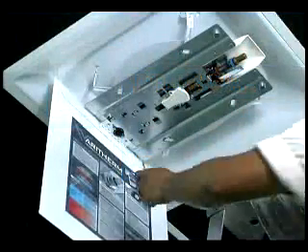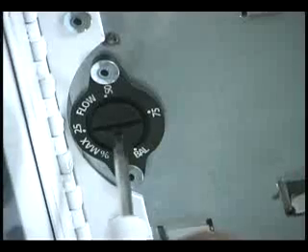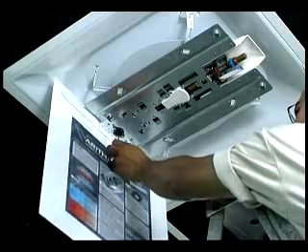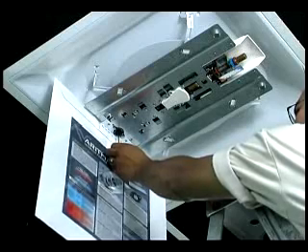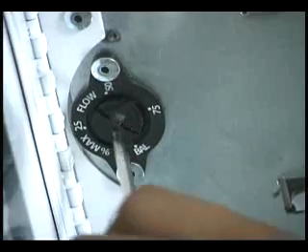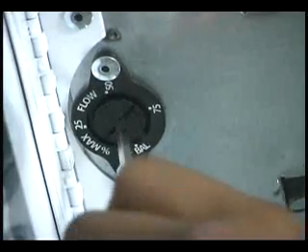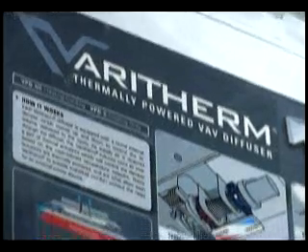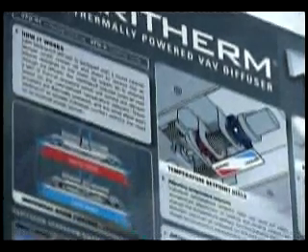The Price Varitherm thermally-powered VAV diffuser is also equipped with a user-friendly minimum airflow adjustment. This simple dial is mounted to the bottom side of the diffuser, allowing the user to adjust the minimum airflow. For system balancing, forced open mode is easily set by turning the minimum airflow dial to indicate BAL.